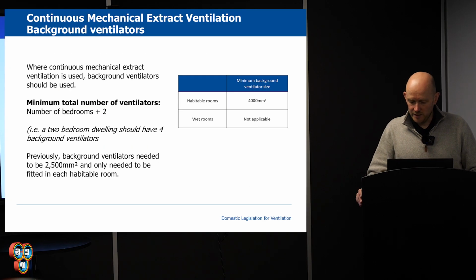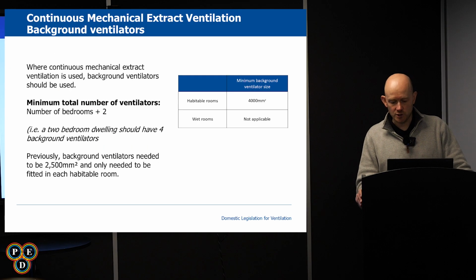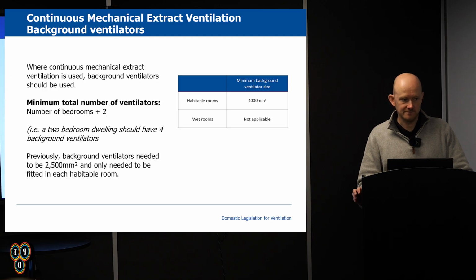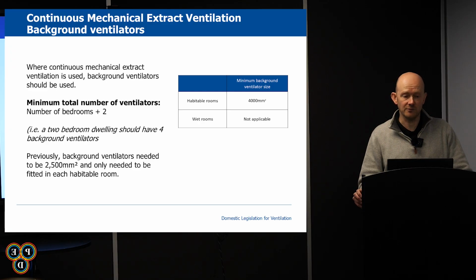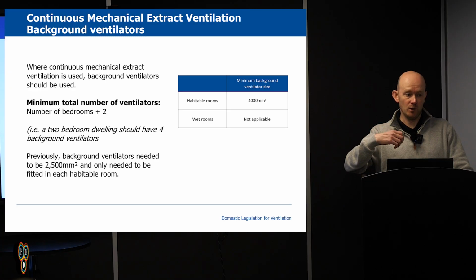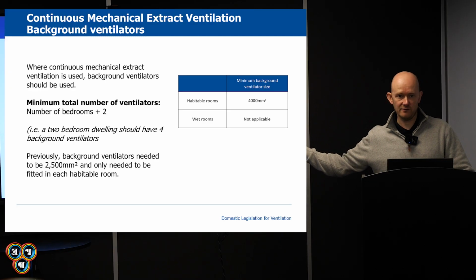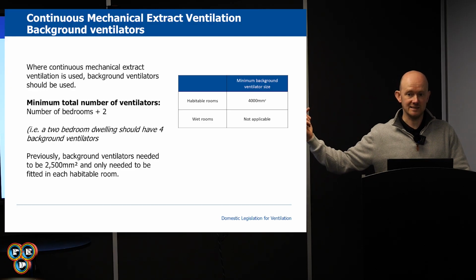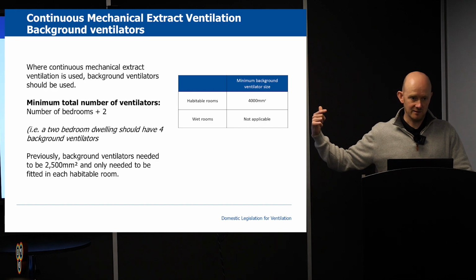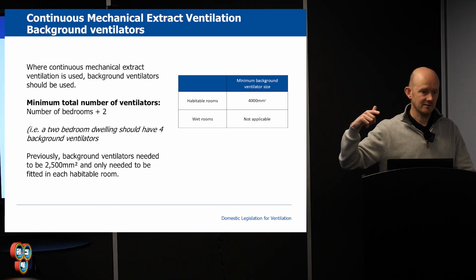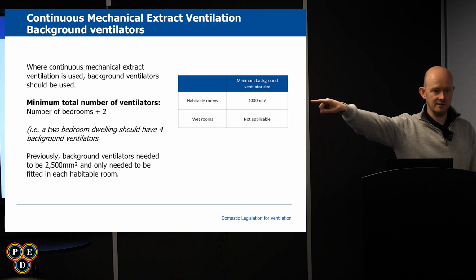And if the fans aren't loud, run it a bit faster if there's higher occupancy. Background ventilators should be installed in habitable rooms, but shouldn't be installed in wet rooms. Now, window manufacturers just whack them in every window. They'll whack them in the bathroom, the utility room, and the kitchen, but you don't. The idea is you don't put them in there. The extractor fans pull out of those spaces. They draw the air from within the property, as in the habitable spaces. The habitable areas provide the fresh air. It goes out through the kitchen, the utility, the WC.